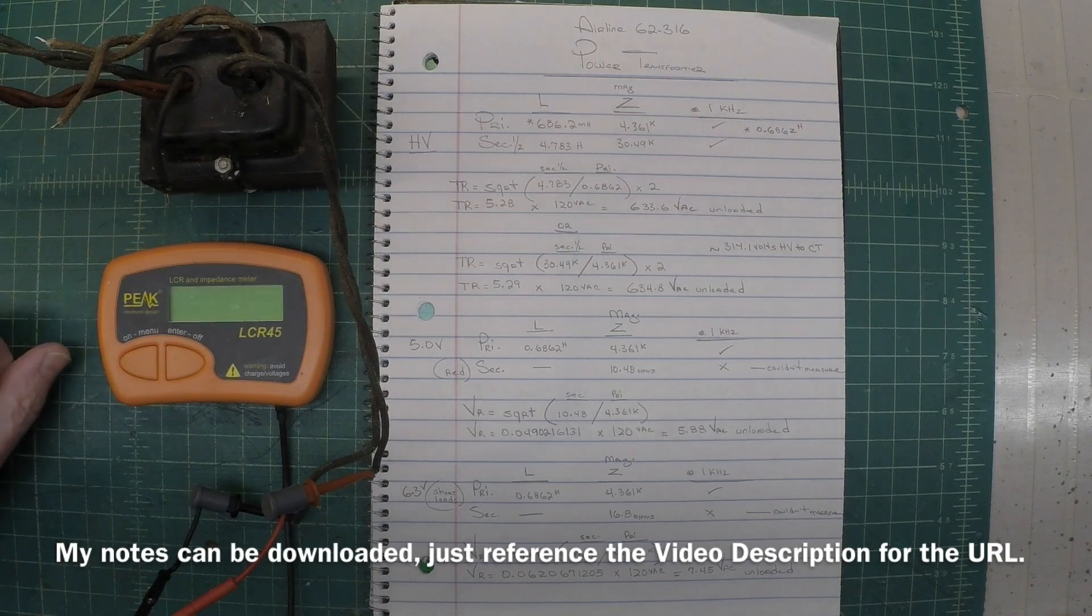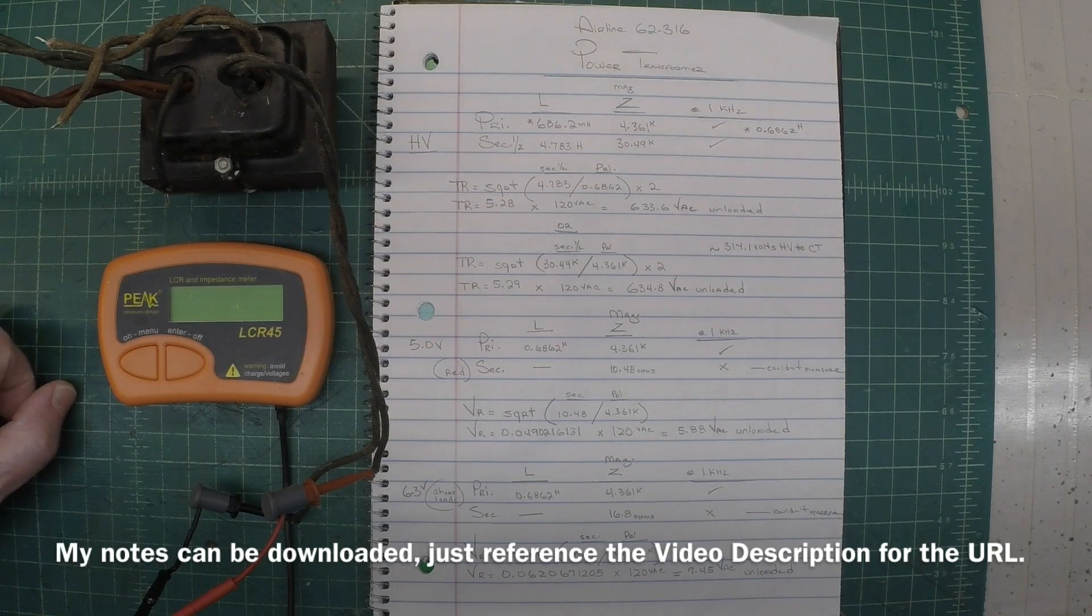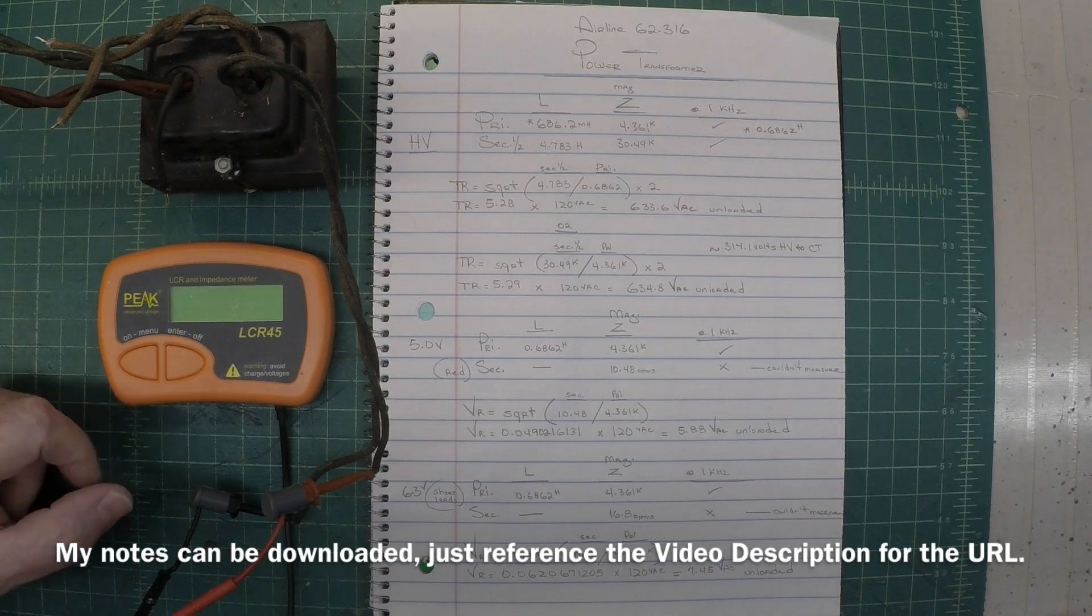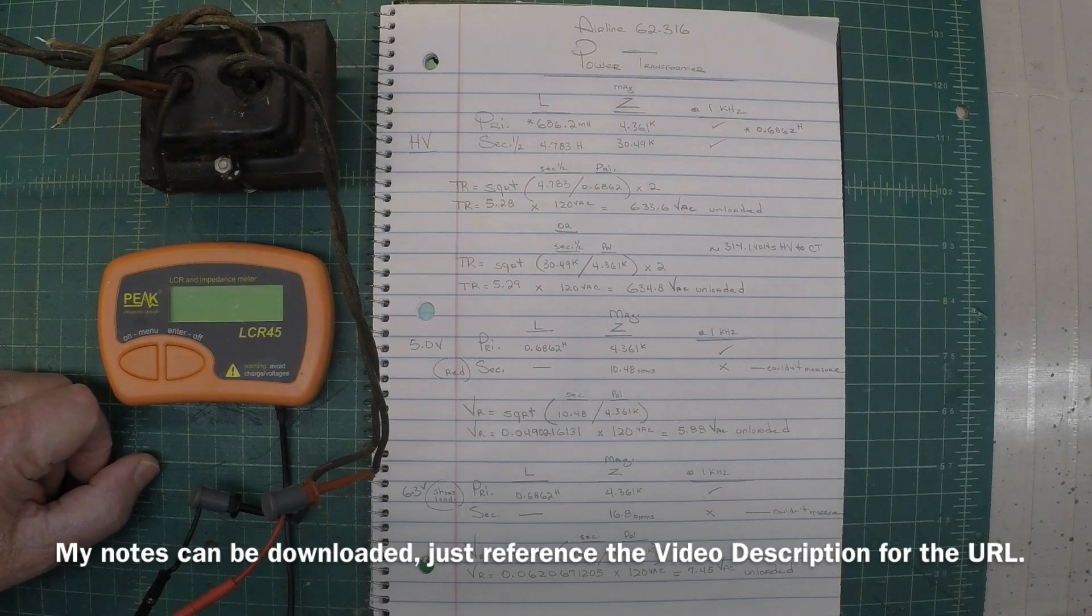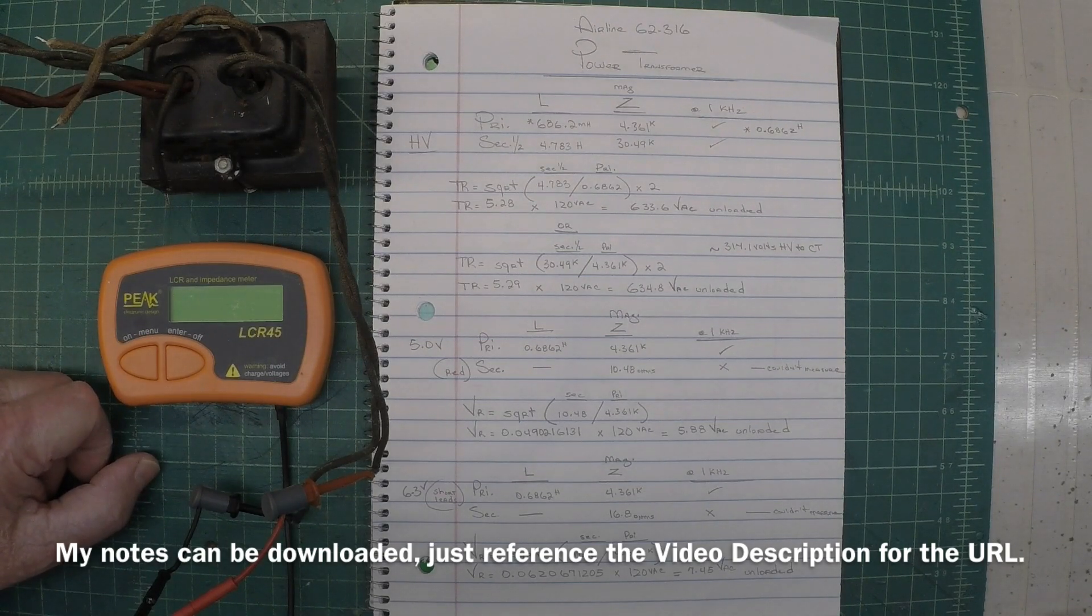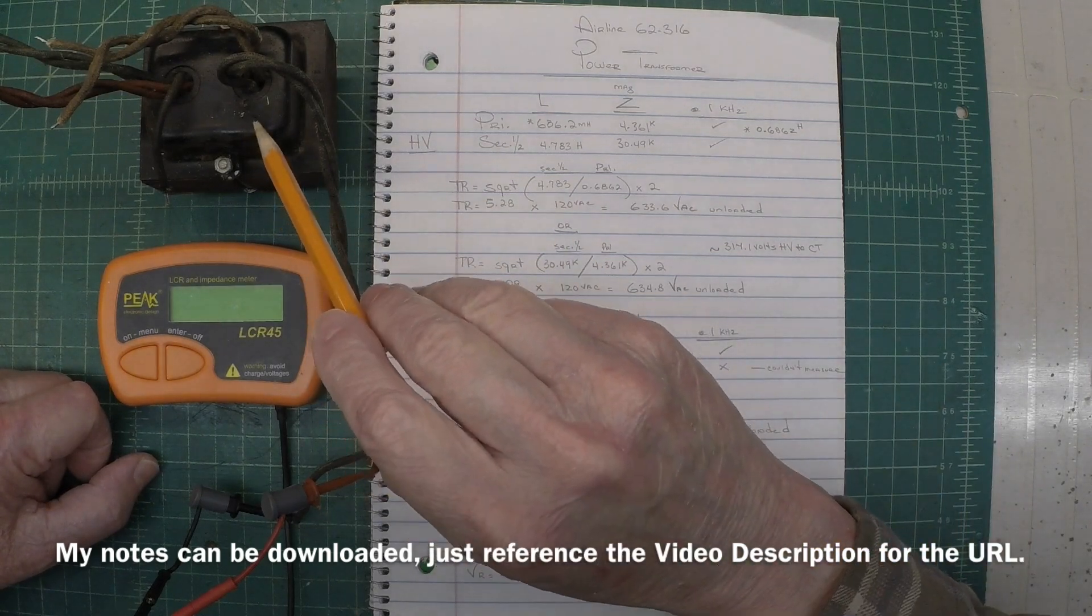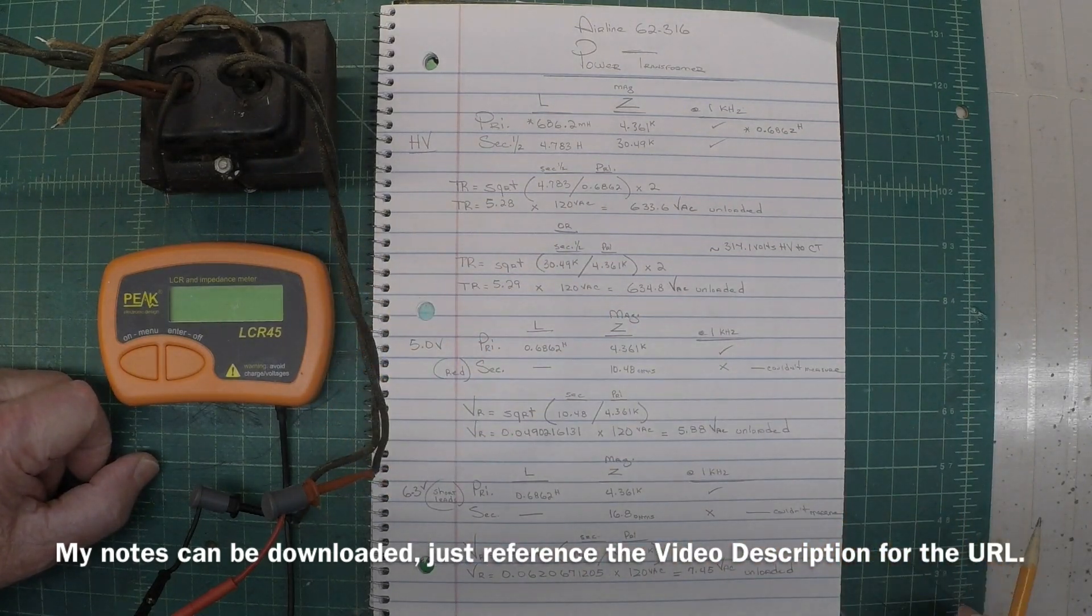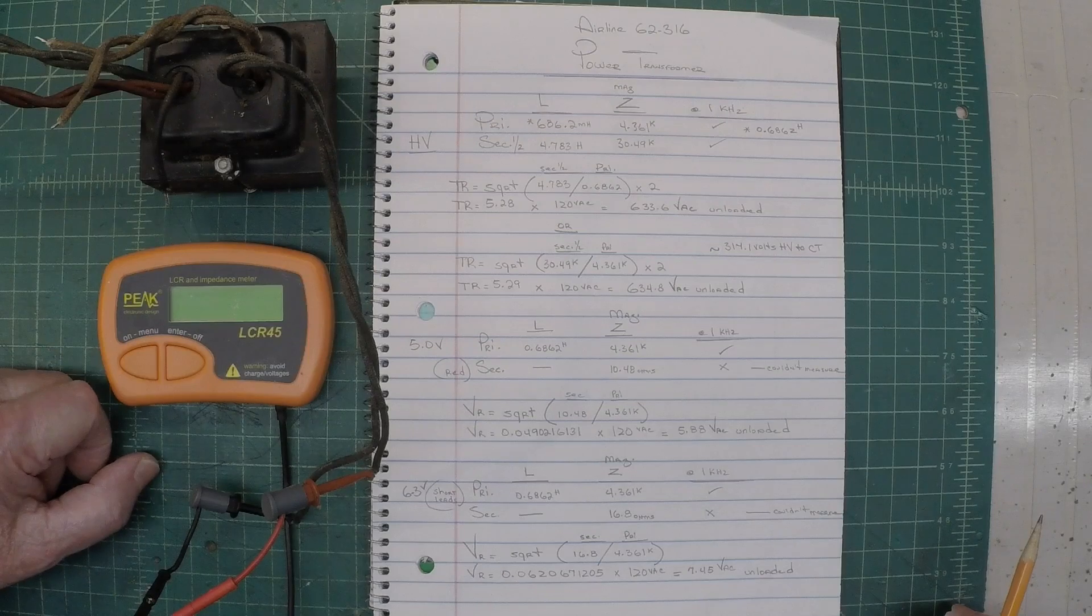I'll show you another feature on the Peak LCR meter, that being the LCR 45, that you can utilize to calculate the turns ratio and the voltage ratio, and back into what the estimated voltage would be of the power transformer unloaded.